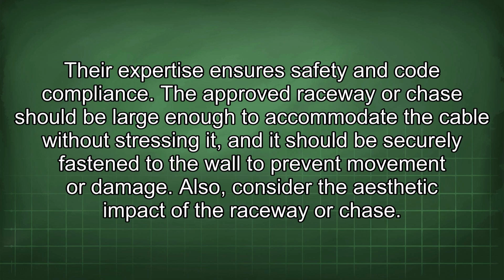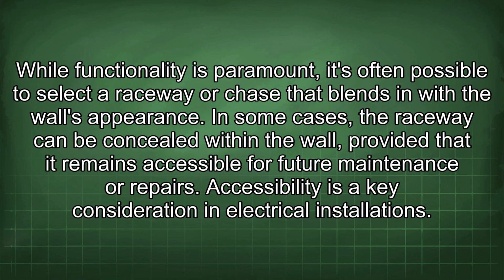The approved raceway or chase should be large enough to accommodate the cable without stressing it, and it should be securely fastened to the wall to prevent movement or damage. Also, consider the aesthetic impact of the raceway or chase. While functionality is paramount, it's often possible to select a raceway or chase that blends in with the wall's appearance. In some cases, the raceway can be concealed within the wall, provided that it remains accessible for future maintenance or repairs. Accessibility is a key consideration in electrical installations.